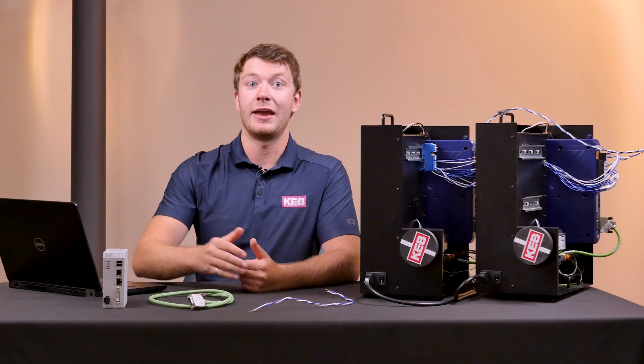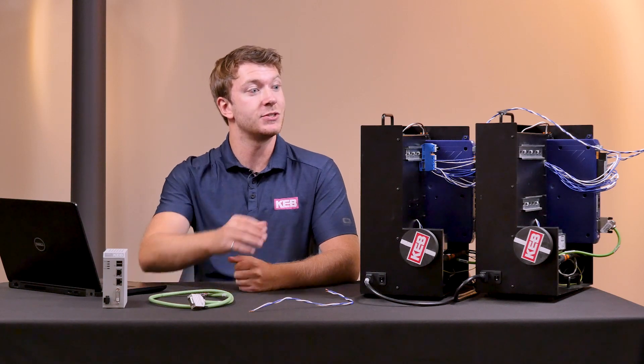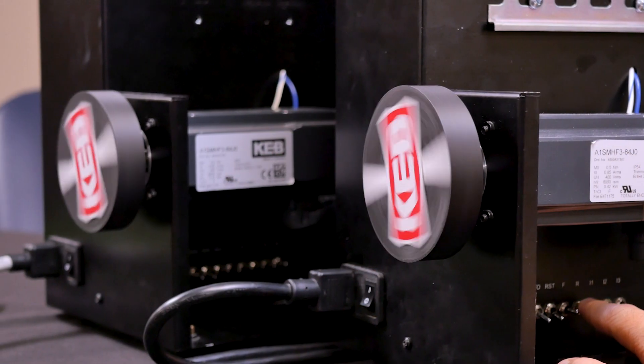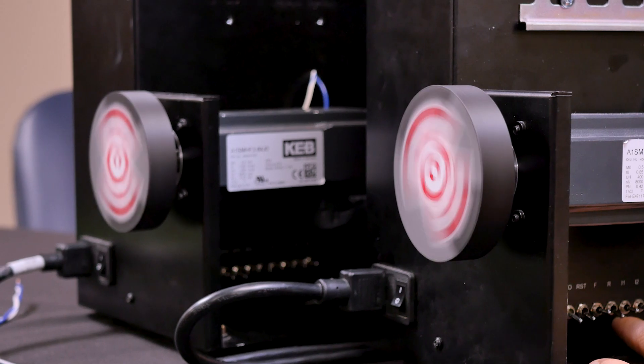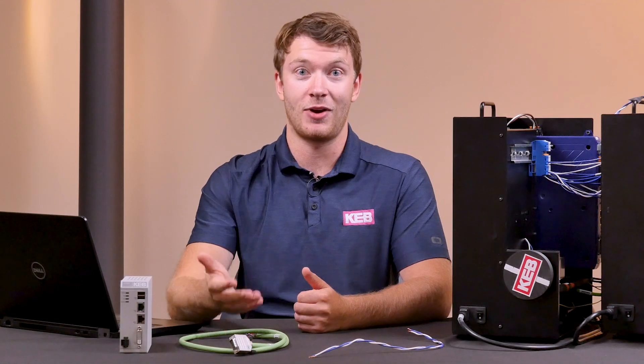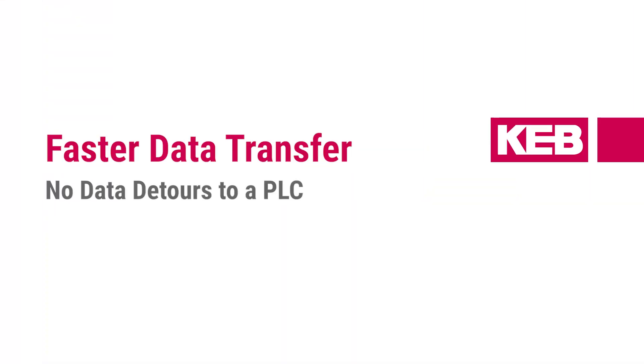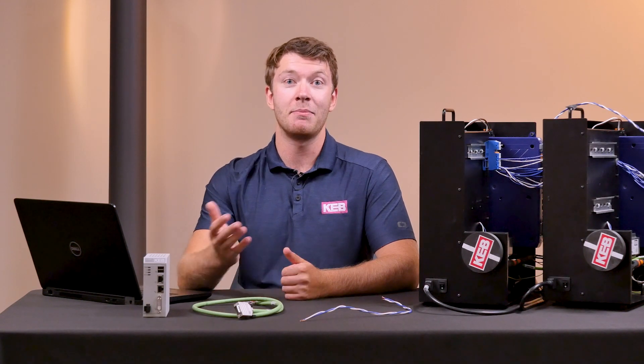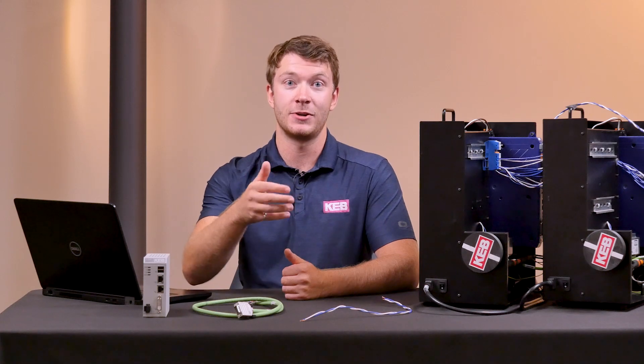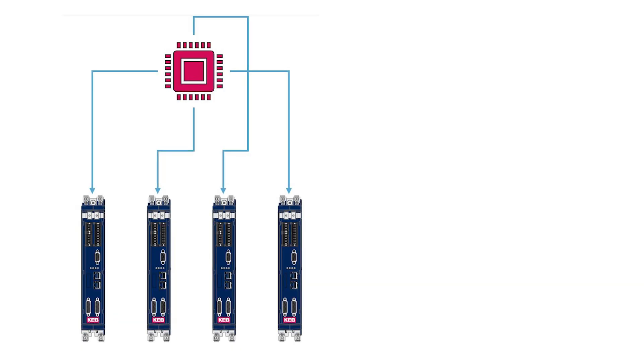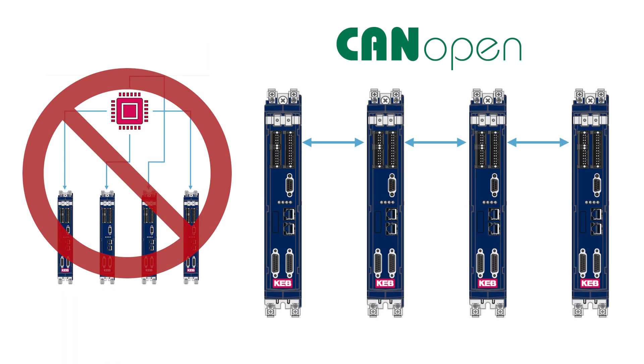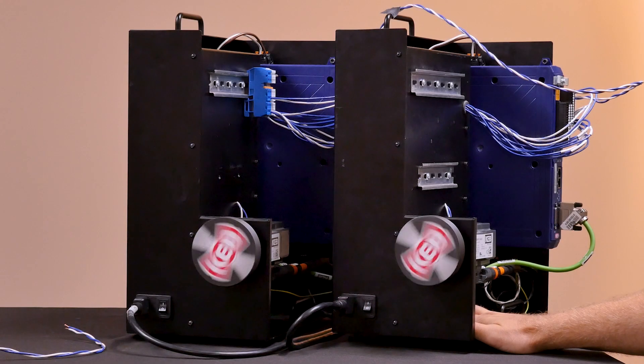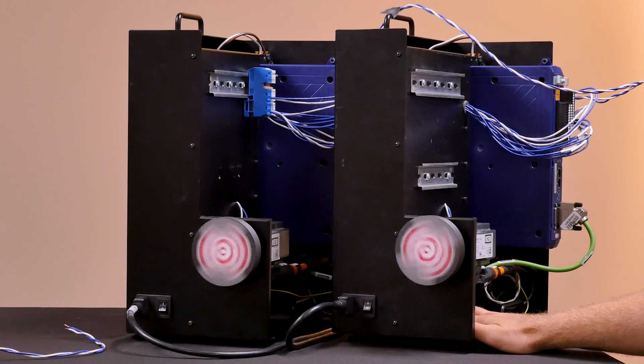What CANopen cross-communication does is allow one of the KEB drives to act as a master in the system, decreasing reliance on the PLC to manage network traffic. Not having the PLC allows for faster data transfer, because messages aren't required to take the data detour of going to the PLC and then back to the drives. Data can go directly between them, which increases the speed of the system and also increases the shaft performance of the drives.